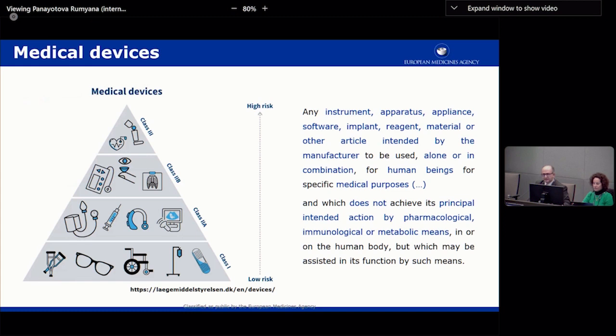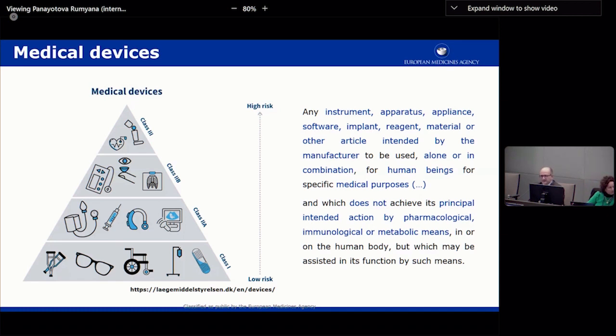Just for context, medical devices cover a huge, broad range of products. The two main aspects to consider for whether or not to classify a product as a medical device have to do with its intended purpose — the product must have a specific medical purpose as defined in the regulation — and also the mode of action, meaning it cannot have its principal mode of action based on pharmacological, immunological, or metabolic means, as that would make it a medicine.